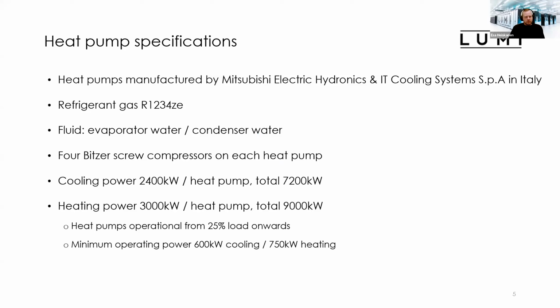Then some specifications about our heat pumps. These heat pumps are manufactured by Mitsubishi Electric Hydronics and IT Cooling Systems SPA, and those are made in Italy. The refrigerant gas that is used is R1234ze, which is a multifunctional gas with low global warming potential and ozone depletion potential. It is displacing and has displaced the previous R134A gas, because this has a much lower environmental impact and good thermodynamic performance. The fluid that we are running in the heat pump is water on the evaporator and condenser side, so there are no other chemicals involved.